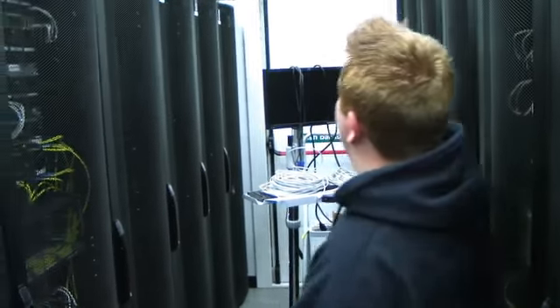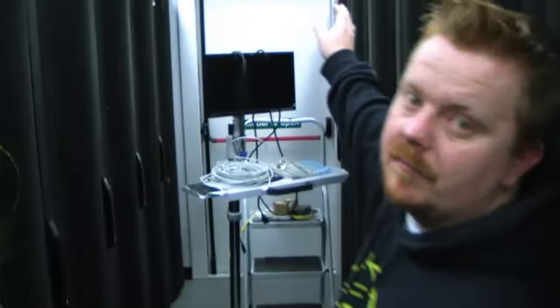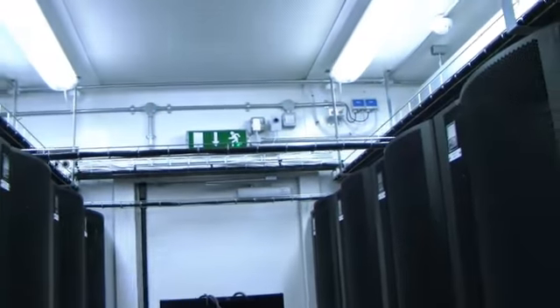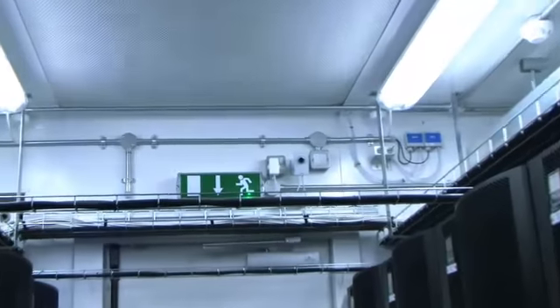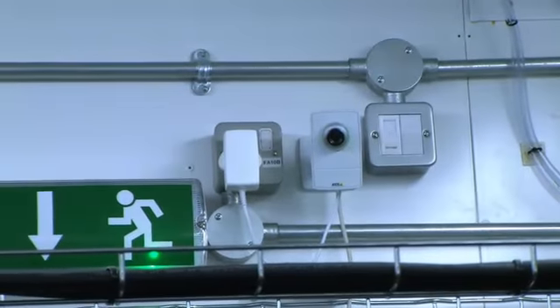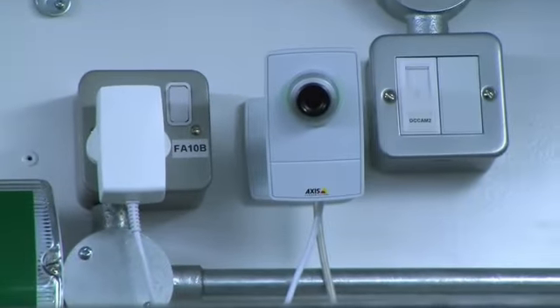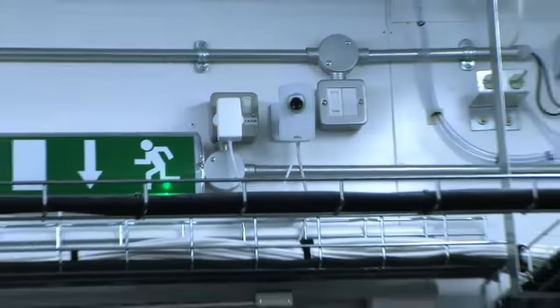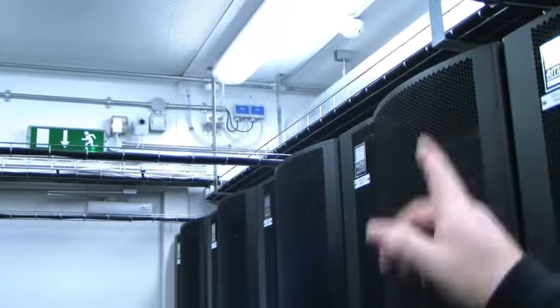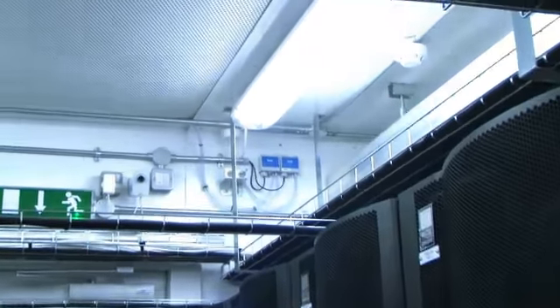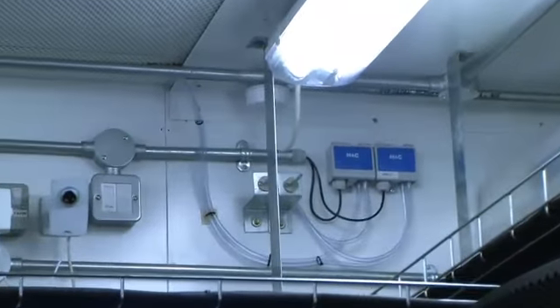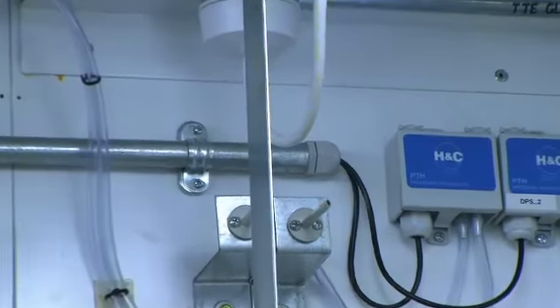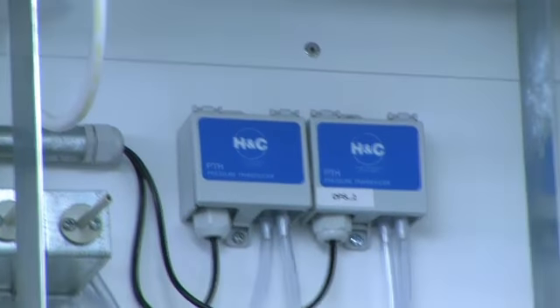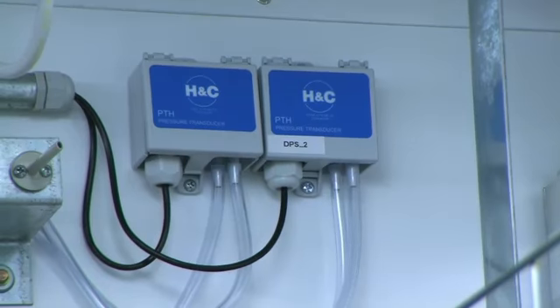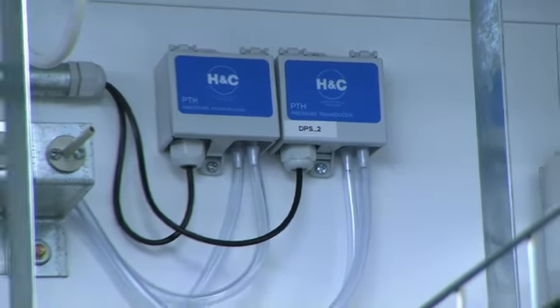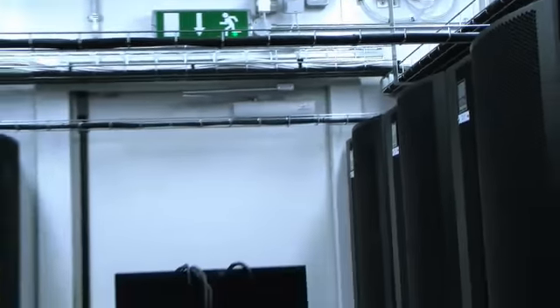We have CCTV cameras at the appropriate locations. They're IP, they're streaming 24/7, 365, and recorded. We have emergency fire exits. We have differential pressure sensors at either end of the building. If you see the plastic pipes coming out of those H&C modules on the wall, they're detecting the pressure difference between upstairs and downstairs. Because obviously above us there is a giant AHU, which is an air handling unit as such.